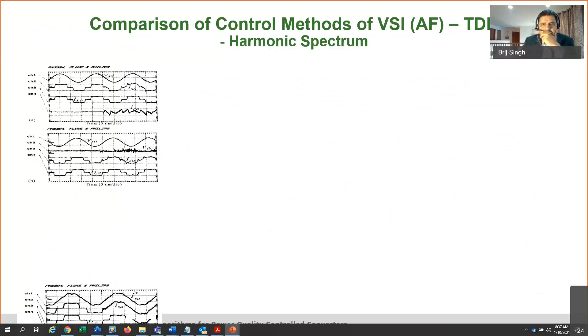If I remember correctly, I used somewhere from 2 kilohertz up to 5 kilohertz. Those were IGBTs from that era, and since this is a 60 hertz system, switching anywhere in the 2 to 5 kilohertz range is good enough.